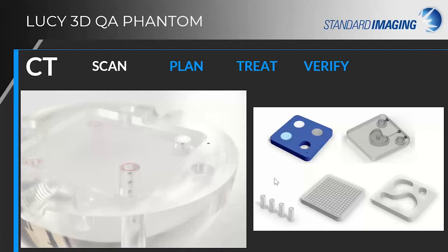So for the CT imaging, we have the CT marker cylinders. We have irregular volume inserts. We have a spot check of the CT densities. Again, not the full 19 plugs, but when you're doing it, you want to do a spot check. So the blue is water equivalent. You have air, adipose fat, trabecular, and cortical bone. CT scan tests may include various scan thicknesses to find the optimal thickness for your SRS imaging, spacing, distortion, and phantom orientation.